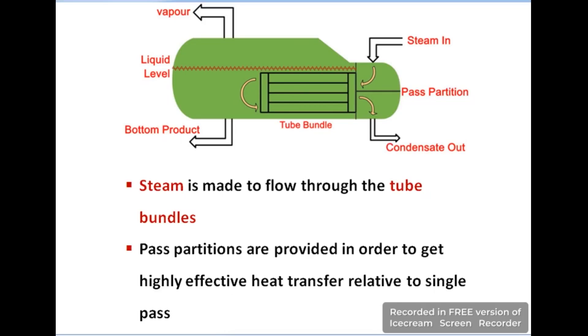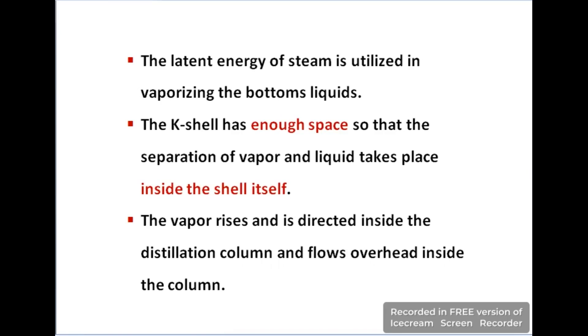Steam is made to flow through the tube bundle. In the diagram, you can see the steam entering the tube bundle. A partition is provided in order to get highly effective heat transfer. The steam running in the tube bundle provides latent energy, and that energy is transferred into the liquid which is outside the tubes in the K shell.